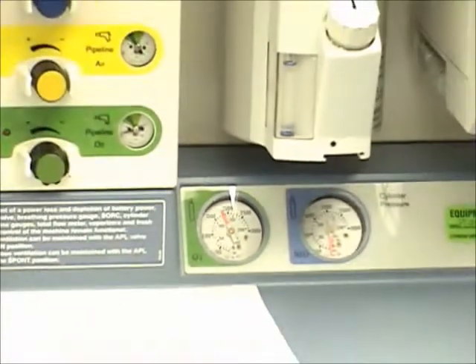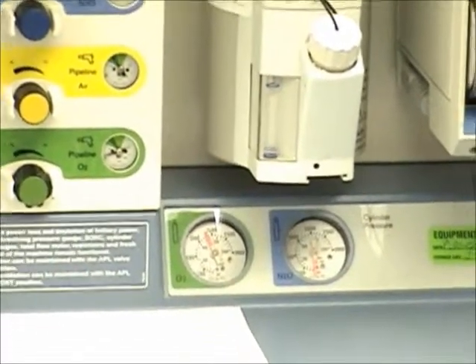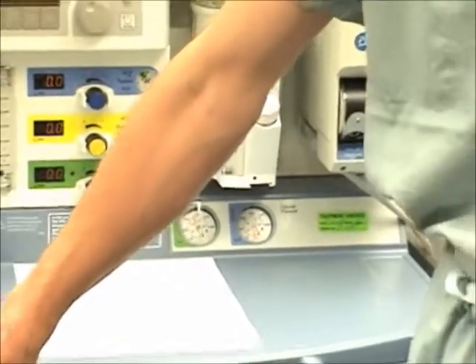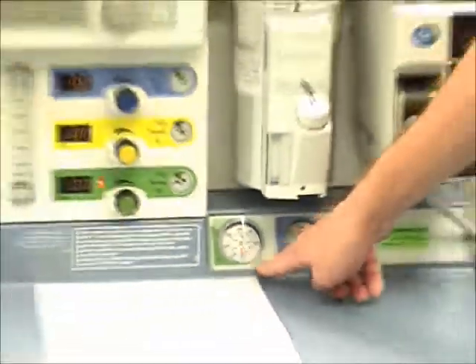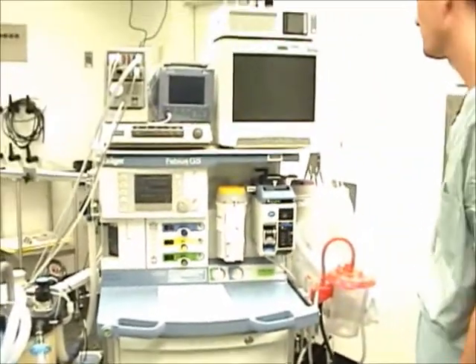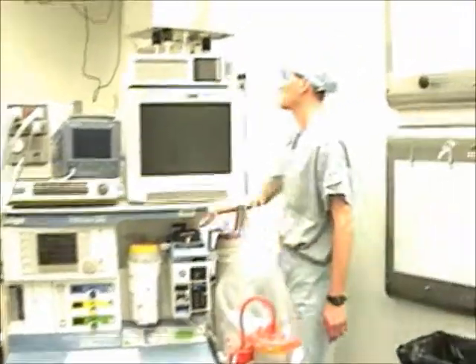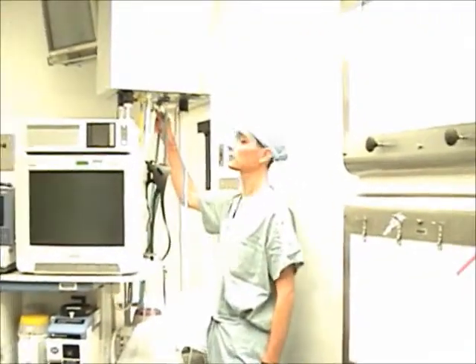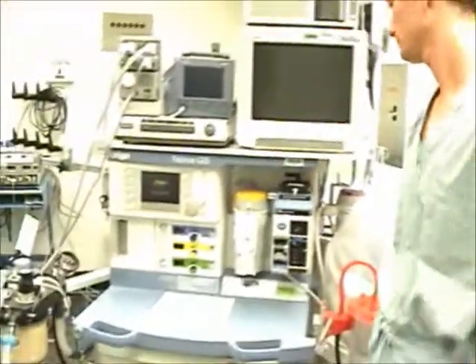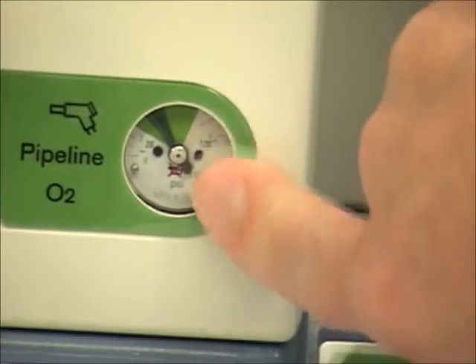Close the reserve oxygen gas cylinder. Bleed the system by pressing the oxygen flush until the gas flow stops. The reserve oxygen gas cylinder gauge should read 0. It reads 0. Insert the pipeline supply hose adapter to the corresponding wall fitting and ensure tight connection. The oxygen pipeline supply pressure gauge should now read within the dark green zone of the gauge.